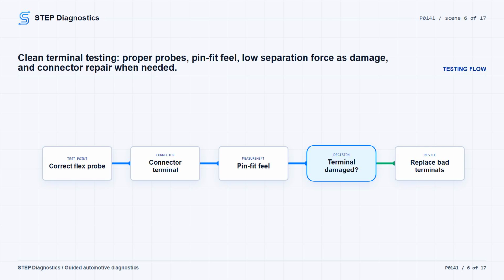If a small pin has to come out of the connector hardshell, pin guide, or retainer to remove extra drag during that check, do that as needed. Replace damaged connectors, pins, or terminals. Do not force probes into connectors. Make a clean test connection without spreading or damaging terminals.